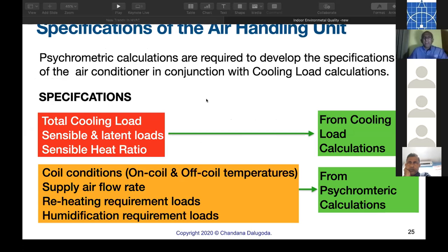Now finally, the specification of the air handling unit. You can see the specification of the air handling unit. What are the specifications? Total cooling load, that is sensible and latent loads, and sensible heat ratio. How do you find this? We have to do proper cooling load calculations. Even though we discuss and educate the manual method, that is here to understand only. Everybody has cooling load calculation these days: computerized methods, hourly analysis programs, or many other programs, not freely available though, but you can purchase. Well, so we run cooling load calculations to get these things properly, or an Excel sheet with the ASHRAE CLTD method.